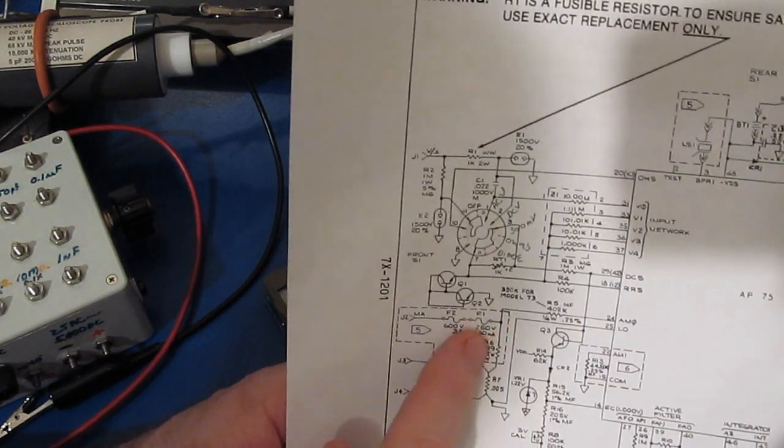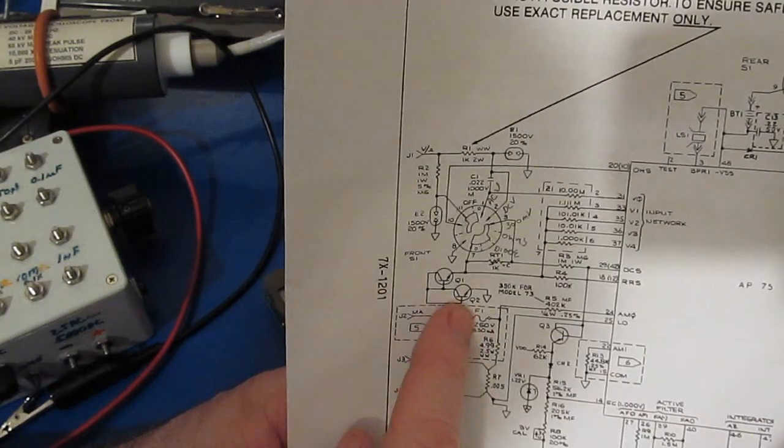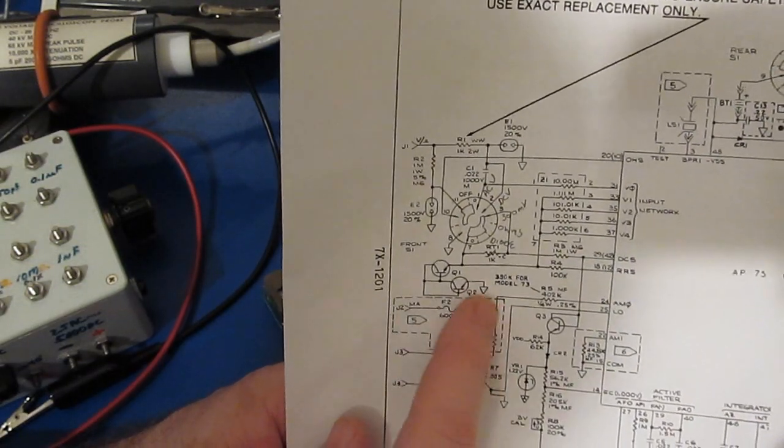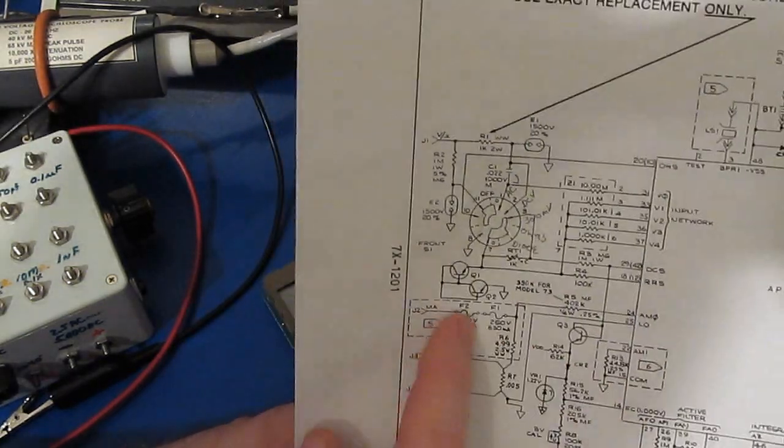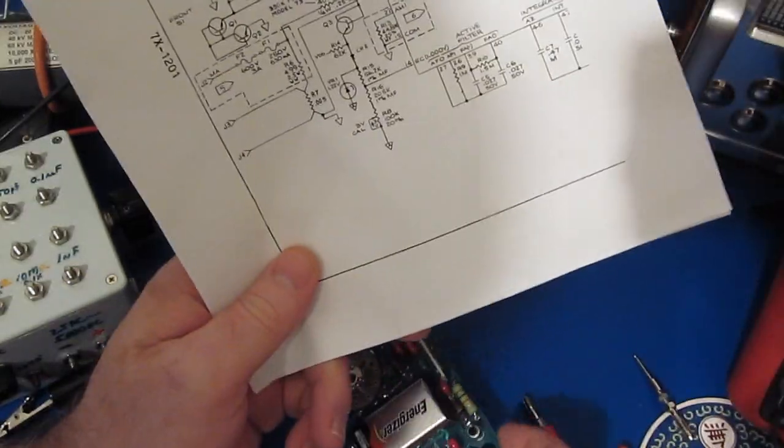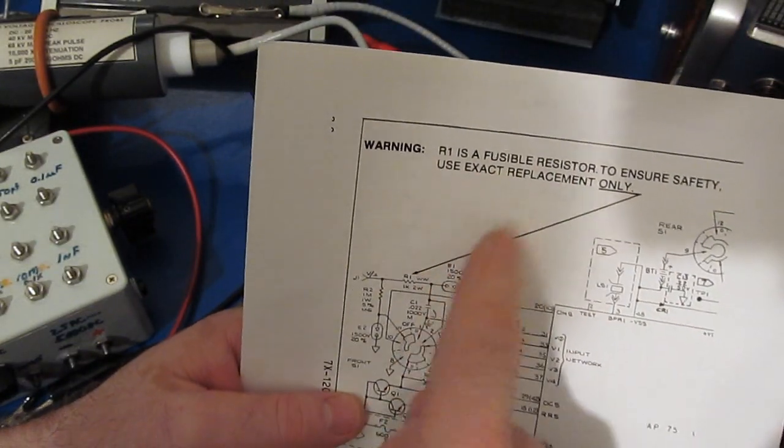In the newer meters they replace this fuse with a resistor and I guess that probably keeps this one from rupturing. And some of the later meters they show this is a larger body style fuse. And then in the newer ones after that it goes back to this smaller case size like we see here.